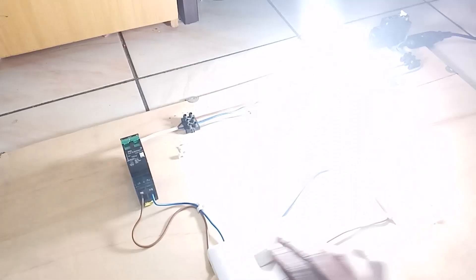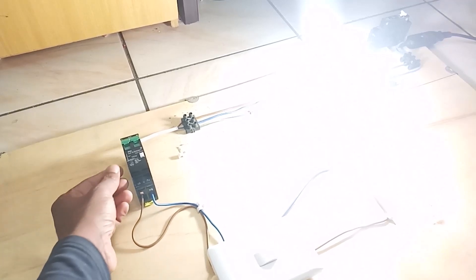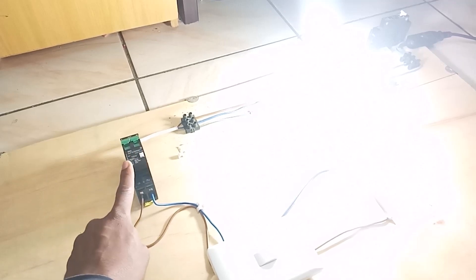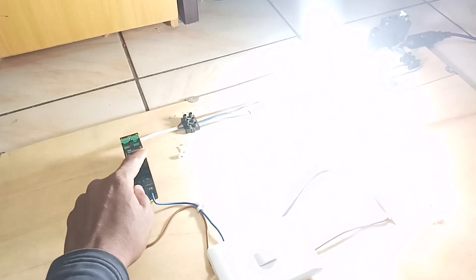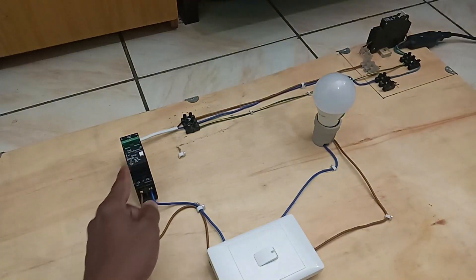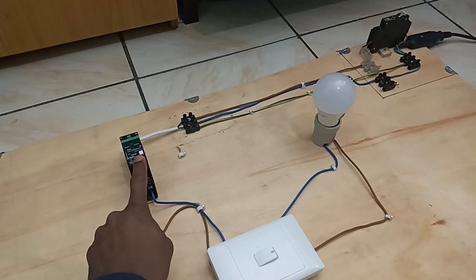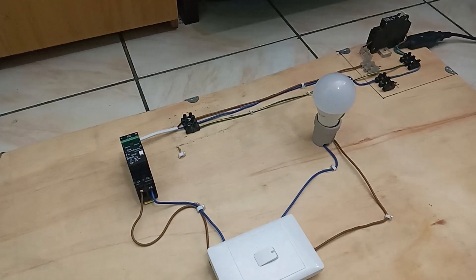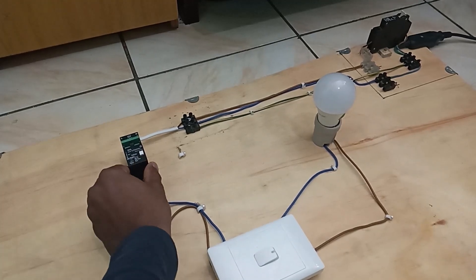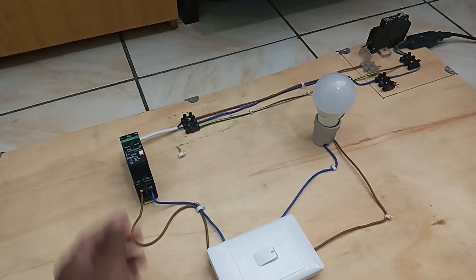So now my light is still working. Now let's go ahead and give a test to the earth leakage breaker. The big moment that we were waiting for. So now when I press this white button here, the circuit should trip. If it doesn't, then I know this thing is broken. So let's go. There we go. So now I pressed it and the light went off. So which means the earth leakage breaker is indeed working.